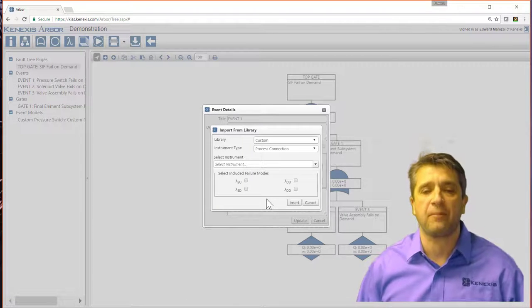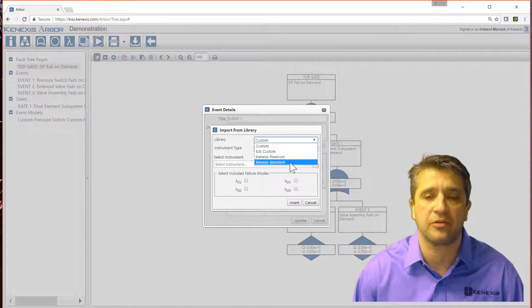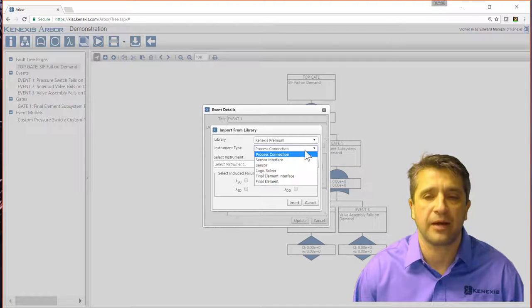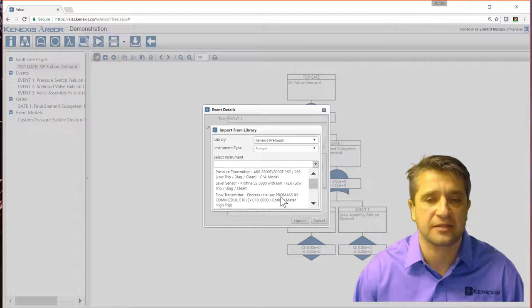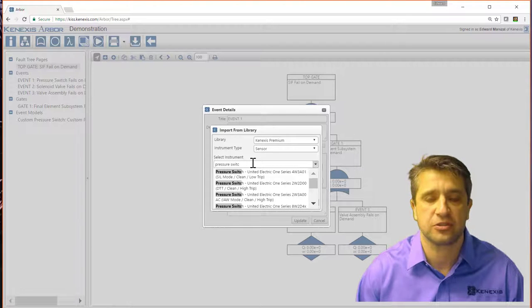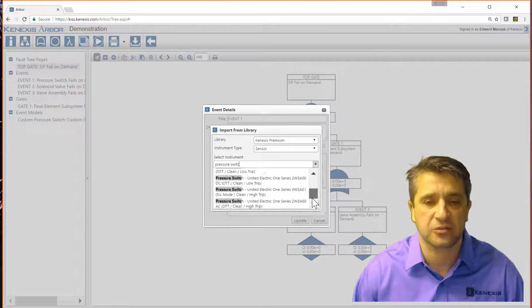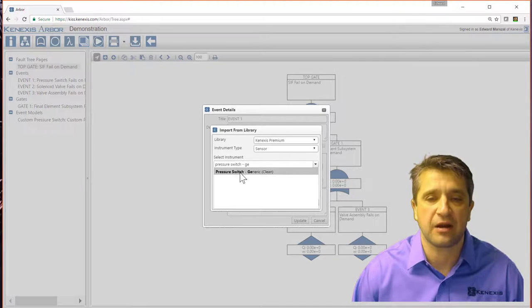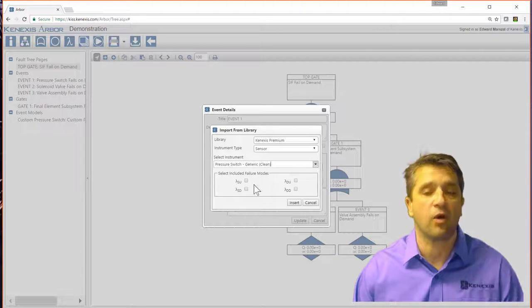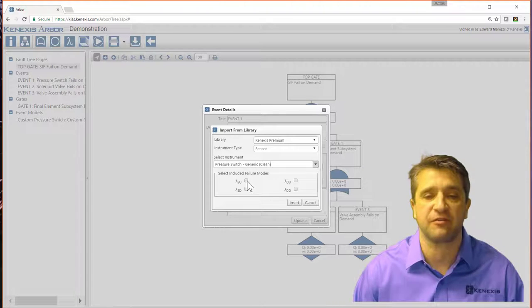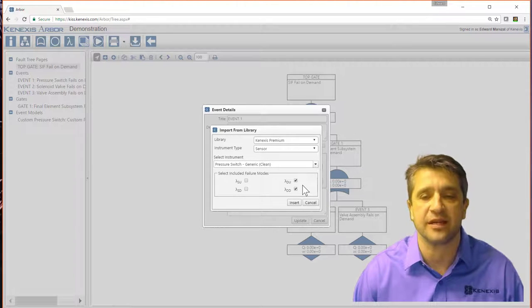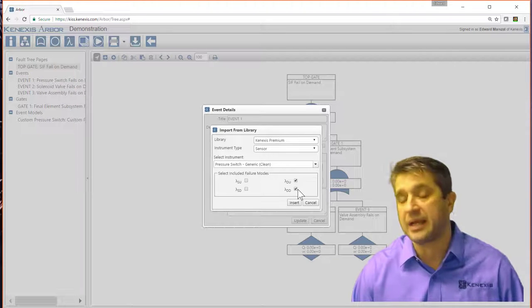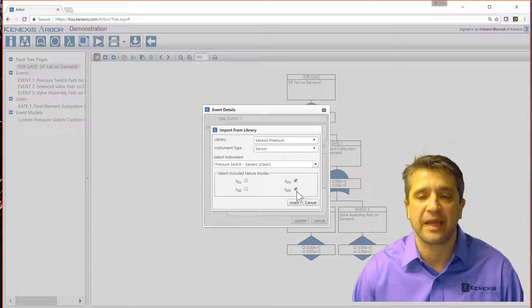When I click that, it's going to pop up the libraries that I have access to. Let's say I want to go into the Kenexis Premium library for sensors. And I want to select, let me see if I can find pressure switch. So we've got a long list of pressure switches available. Let me just put generic in. So generic pressure switch in clean service. Then I want to select, which failure modes do I want to track for this specific event? In this case, it's going to be dangerous undetected and dangerous detected.